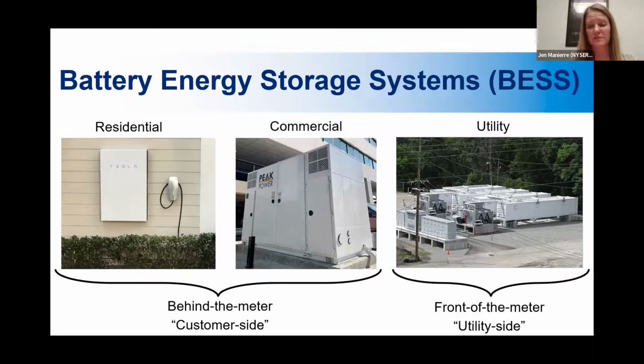On the other side of things, front of the meter, if you will, quite literally located in front of a meter, or on the utility side, we have the much larger energy storage systems, which are taking electricity out of the grid when it's not needed or when there's an excess, storing it until it is needed, and pushing it right back out onto the grid, just like any power plant might do. And those electrons can just go wherever they're needed. These larger scale utility energy storage systems are not associated with a building or a load in particular. And you can see the difference in size is quite stark. The residential system might be the size of a large suitcase. A commercial system, maybe a refrigerator or a few refrigerators together in size. And for utility, we're looking at shipping containers full of batteries, or even in this case, in this photo, multiple shipping containers for scale.